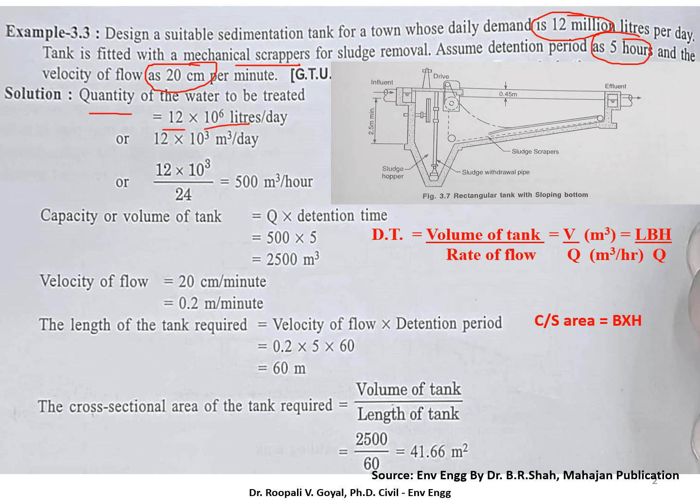First we have to convert the unit to meter cube per hour, because our detention time is normally in hours. So as you know that detention time is given by volume upon rate of flow. So here we know rate of flow and detention time, so we get the volume of tank.